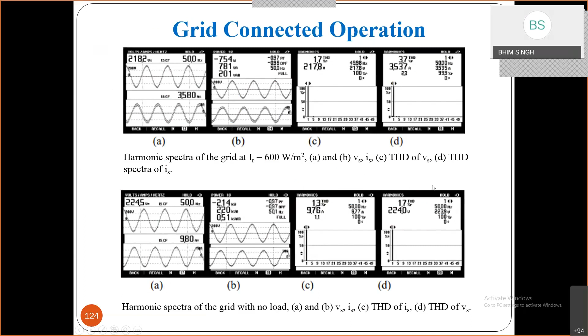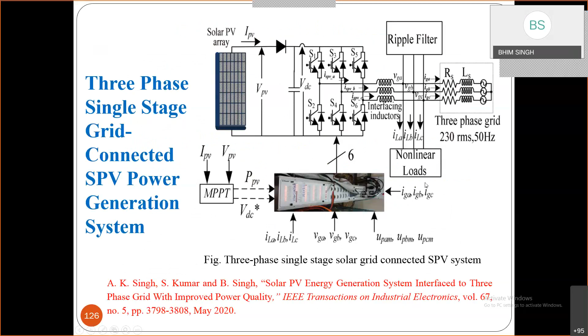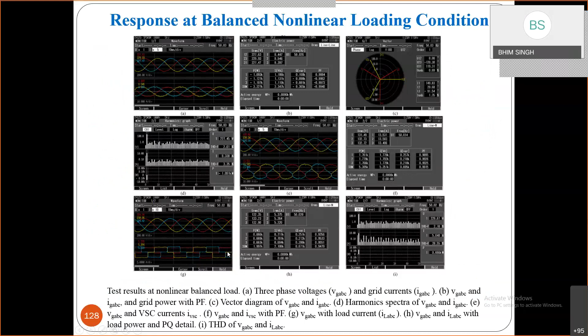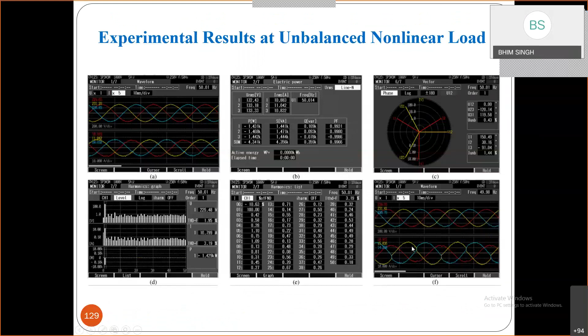Of course, we extended the work to a three-phase system also, with compensation of the local load and supply current almost sinusoidal at unity power factor, even when the solar generation is changing, while compensating the load. All those aspects, we modified the control with advanced methods, and you can see the grid currents are sinusoidal, whereas the load current is quite non-sinusoidal. So the inverter is fitting the local requirement of the load, and even with an unbalanced line-to-line load, the currents are still balanced and sinusoidal at unity power factor.